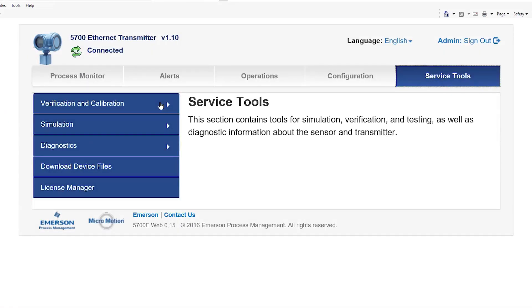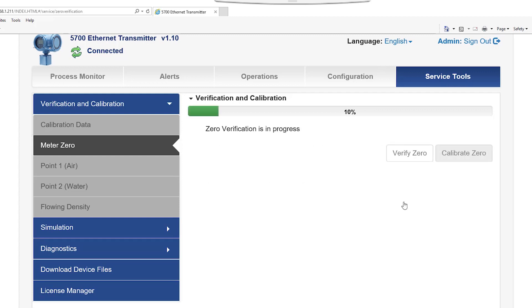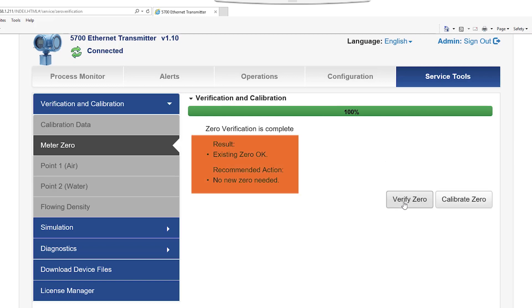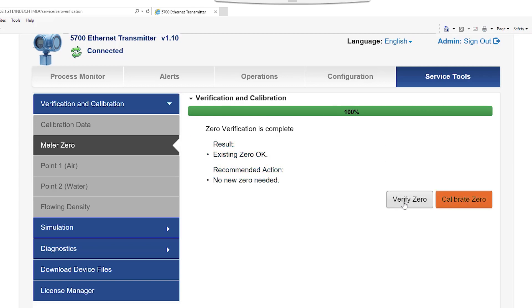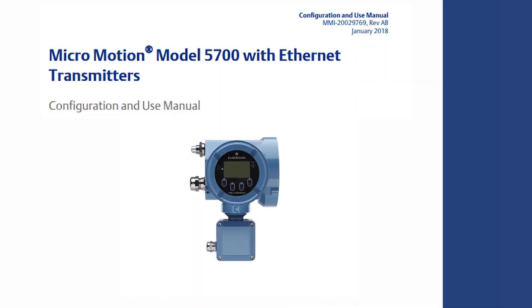The service tools tab contains tools for simulation, verification, and testing, as well as diagnostic information about the sensor and transmitter. The verification and calibration menu allow the user to verify the zero of the meter. If the meter passes zero verification, a new zero is not recommended. If a new zero is recommended, the user can calibrate a new zero, restore prior zero, or restore factory zero. Please follow the complete set of instructions in the configuration and use manual for your transmitter.